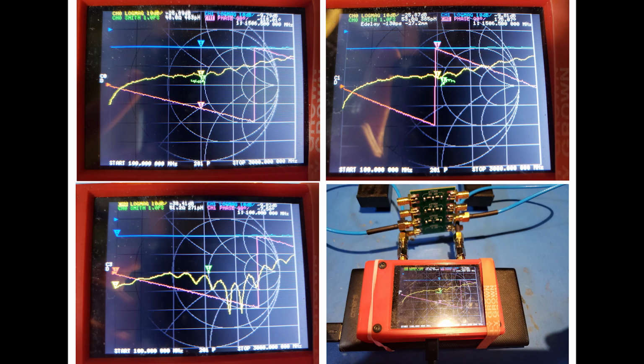If we take a look at the images from the measurements of the 10 dB attenuator here, we see that the female Cal kit standard basically shows us a perfect dot in the center of the Smith chart, whereas there are some differences when we use the stock Cal kit. We can see that applying the port extension significantly changed the phase of S21, but the overall attenuation that we measure for the whole frequency range looks about the same.